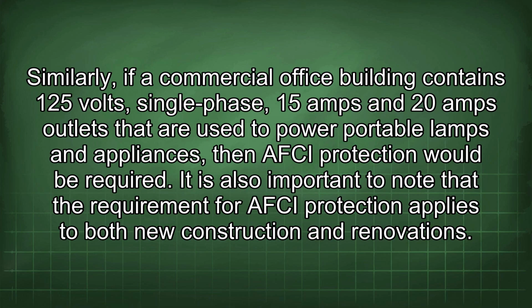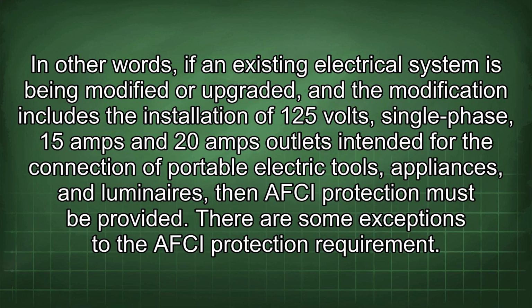It is also important to note that the requirement for AFCI protection applies to both new construction and renovations. In other words, if an existing electrical system is being modified or upgraded, and the modification includes the installation of 125 volts single-phase, 15 amps and 20 amps outlets intended for the connection of portable electric tools, appliances, and luminaires, then AFCI protection must be provided.